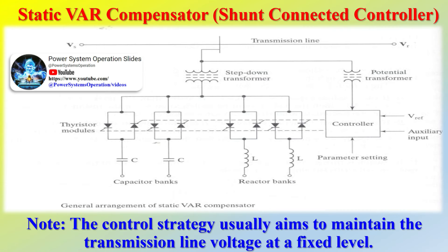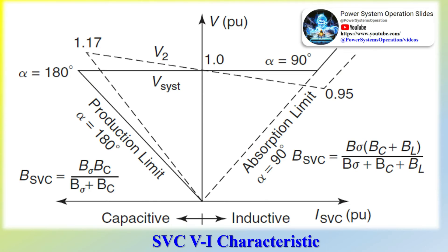A STATCOM has superior performance during low-voltage conditions as the reactive current can be maintained constant. In an SVC, the capacitive reactive current drops linearly with the voltage at the limit of capacitive susceptance. It is even possible to increase the reactive current in a STATCOM under transient conditions if the devices are rated for the transient overload. In an SVC, the maximum reactive current is determined by the rating of the passive components — reactors and capacitors.